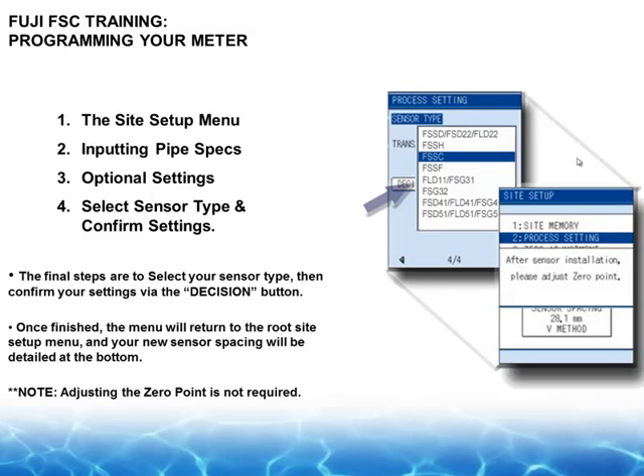And I don't know why these guys say this, people that are in a flow laboratory, little white coats. In the field, it's hard to get a 0 reference unless you went to, say, a sprinkler system or had a standpipe. If you have a flow loop and you close off one valve to your left and one valve to your right, you still get what we call the jello effect, going back and forth, back and forth. This Fuji meter is so sensitive that we program it when we ship it out the door to not see anything less than 1/10 of a foot per second. We program that as a cutoff point. You can change it if you need to, but that's our low flow cutoff because there's just too much data in there, and it affects the performance.